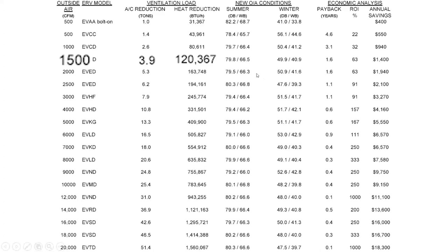Coming off the wheel, this was done for a 95 degree summer day, 95, 76, I think it was, and then a -10 winter day. But on a 95 degree day, I'm going to get 80, 67 off the wheel. On a negative 10 degree day, I'm getting 50 off the wheel, 60 degrees of heat. 80, 67 is not random. We usually size a lot of ERVs for 80, 67. You can get ones that'll do better or worse. Better ones cost more, worse ones cost less. But we target 80, 67 typically because that is the AHRI rating point for everybody's evaporator coil. It's expecting 80, 67 on the inlet of the evaporator anyway. So if I can get there with the outside air, with the ERV, it's like you don't even have outside air from the perspective of the evaporator coil.